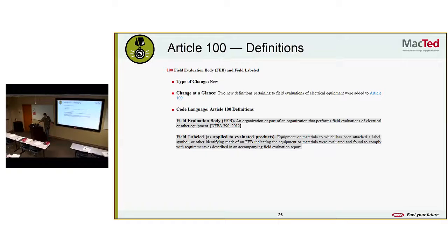Field evaluation body and field label. These are two new definitions pertaining to field evaluations of electrical equipment. They were added to Article 100. Field evaluation body is an organization or part of an organization that performs field evaluations of electrical or other equipment. And field label is applied to evaluated products, equipment or materials to which has been attached a label, symbol, or other identifying mark of an FEB, indicating the equipment or materials were evaluated and found to comply with requirements and described in an accompanying field evaluation report. So like maybe UL rating, or what's the Canadian equivalent? Is that CSA, something like that? Yeah.